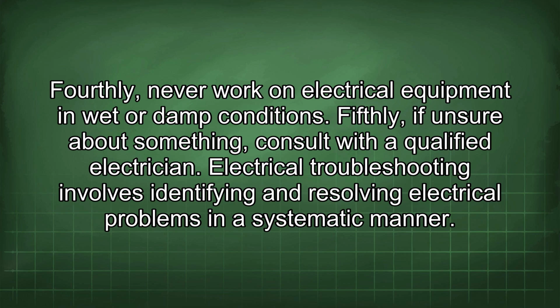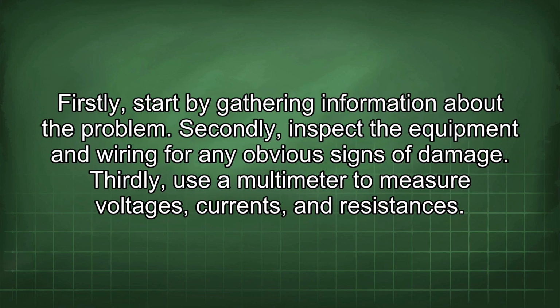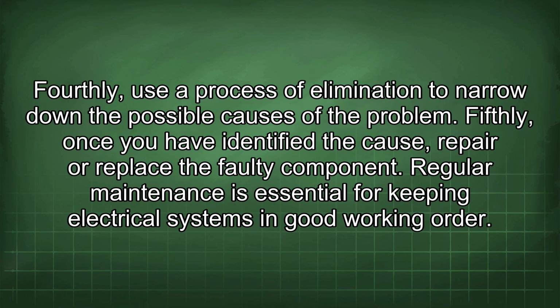Electrical troubleshooting involves identifying and resolving electrical problems in a systematic manner. Firstly, start by gathering information about the problem. Secondly, inspect the equipment and wiring for any obvious signs of damage. Thirdly, use a multimeter to measure voltages, currents, and resistances. Fourthly, use a process of elimination to narrow down the possible causes of the problem. Fifthly, once you have identified the cause, repair or replace the faulty component.